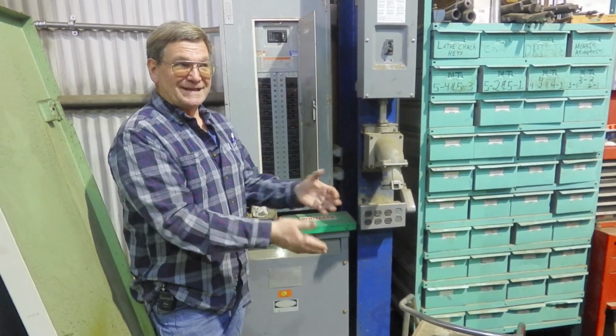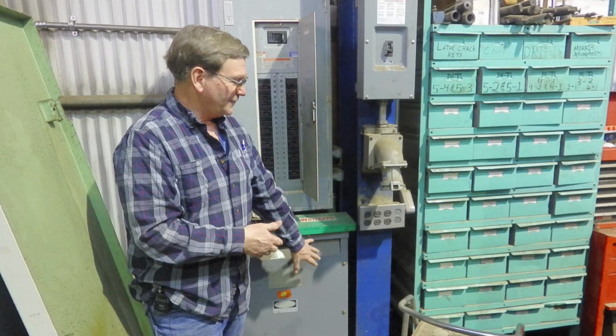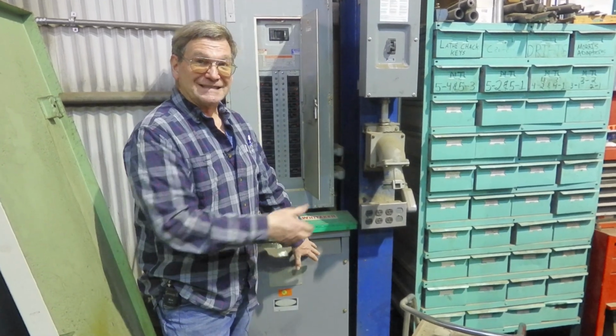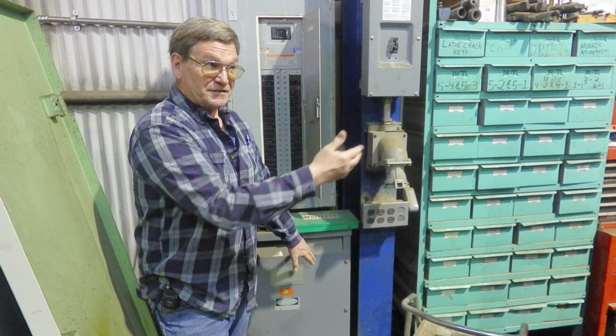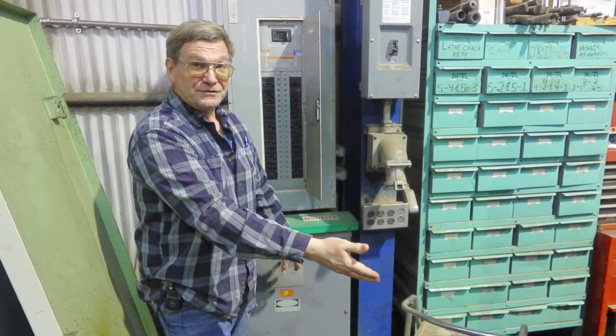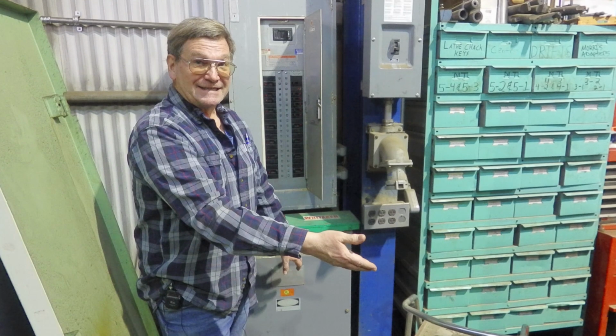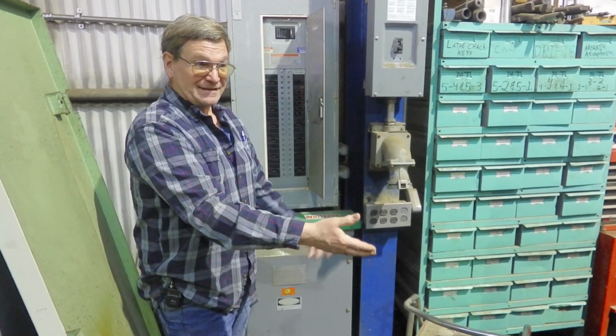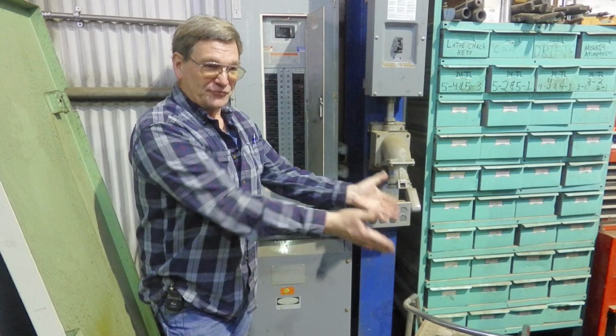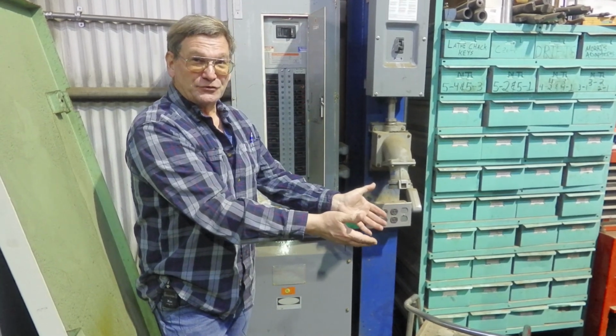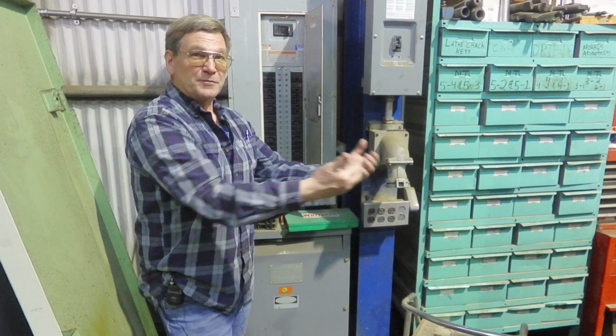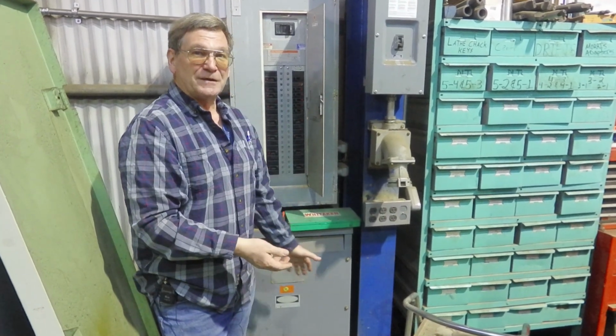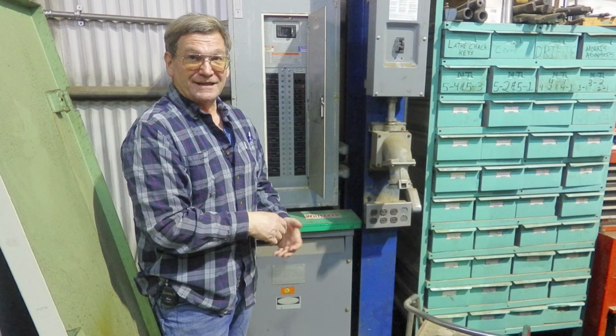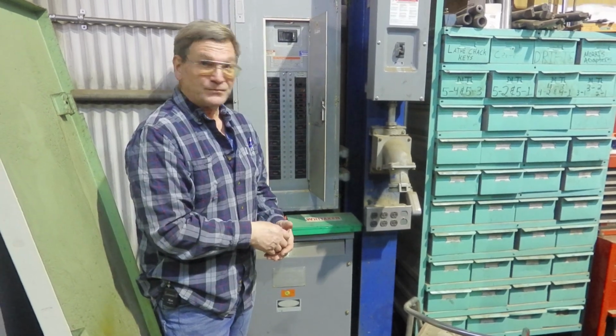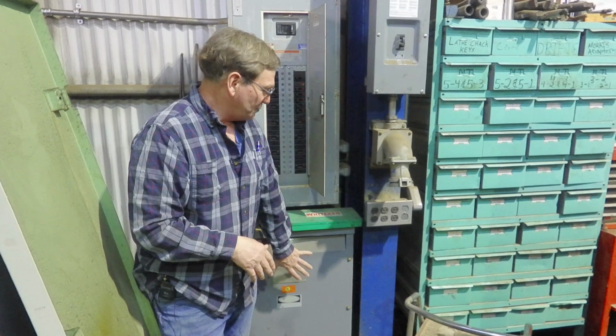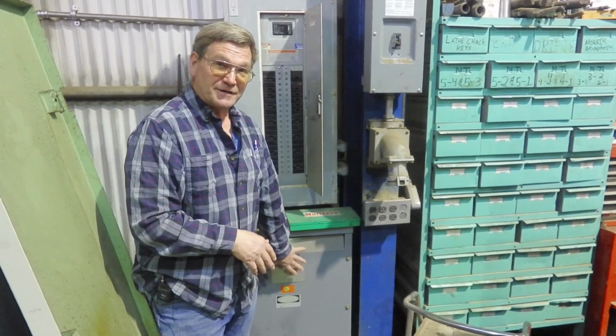The truth is we're taking away a little more, but since we have the taps in here so that we can set this for a higher voltage input. And what that does is that would mean the connection that you'd hook it to if your voltage coming in was higher. So since your voltage is not higher, you hook it up to a higher one and it puts out less. So when it puts out less, it subtracts less off of the 480 volts. So anyway, that allows you to use a good sized transformer as a buck boost transformer.